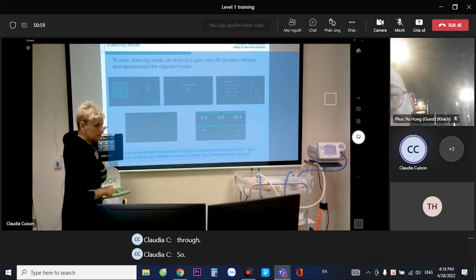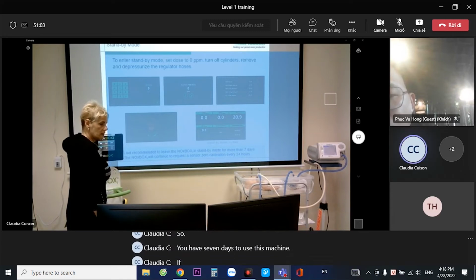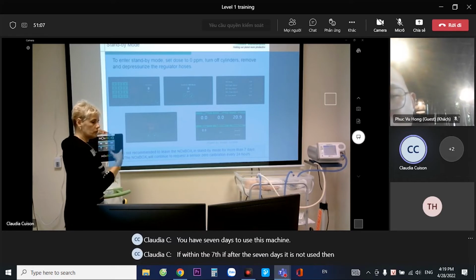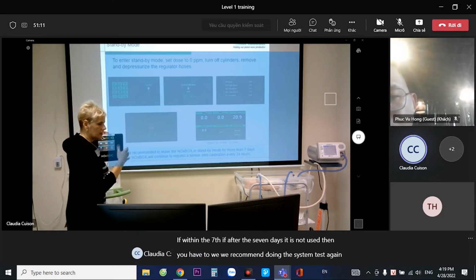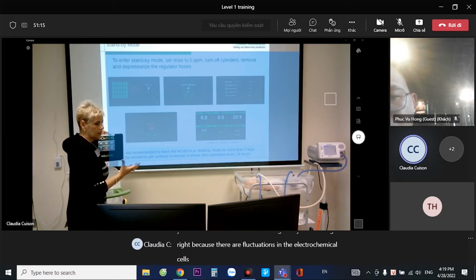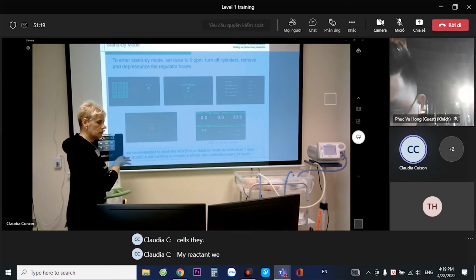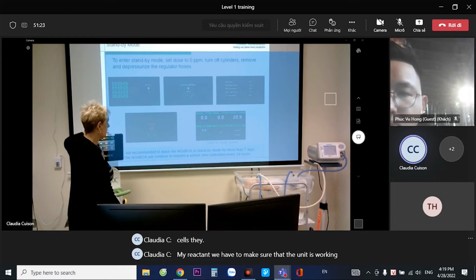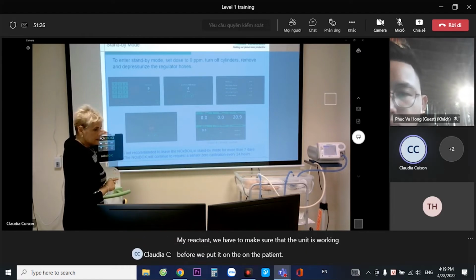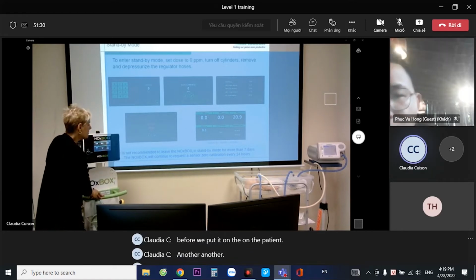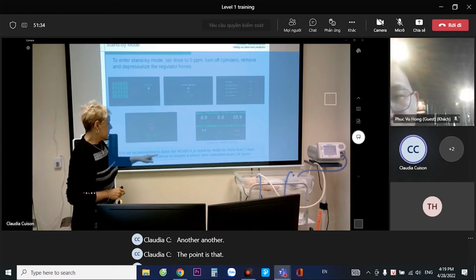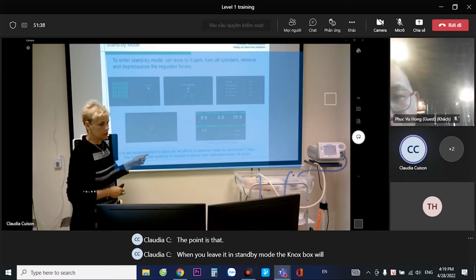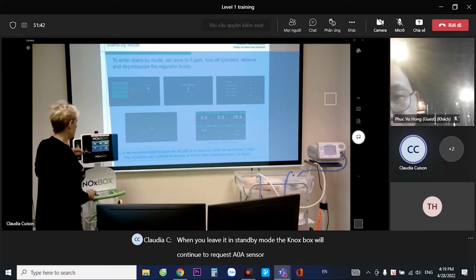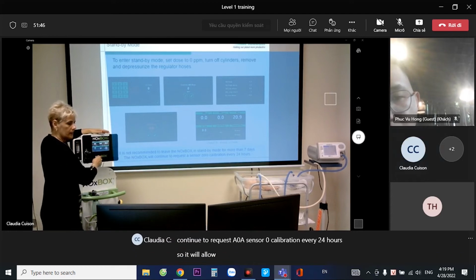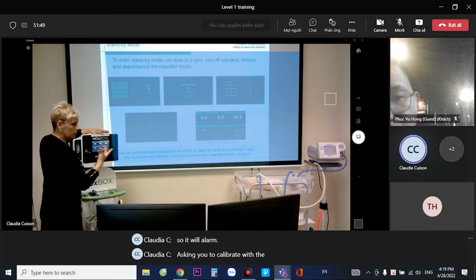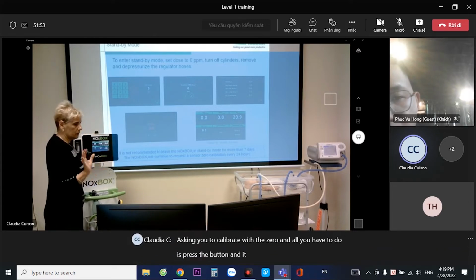So you have 7 days to use this machine. If after the 7 days it is not used, then we recommend doing the system test again, right? Because there are fluctuations in the electrochemical cells. They might react, and we have to make sure that the unit is working before we put it on a patient. Another point is that when you leave it in standby mode, the NOxBOX will continue to request a sensor zero calibration every 24 hours. So it will alarm, asking you to calibrate with the zero. And all you have to do is press the button and it calibrates itself, nothing else.